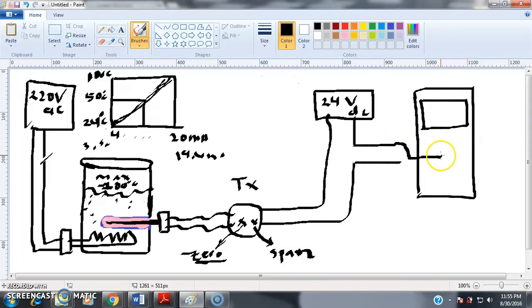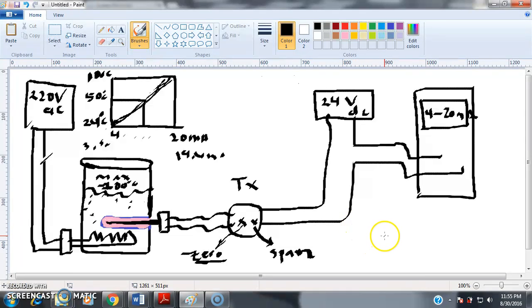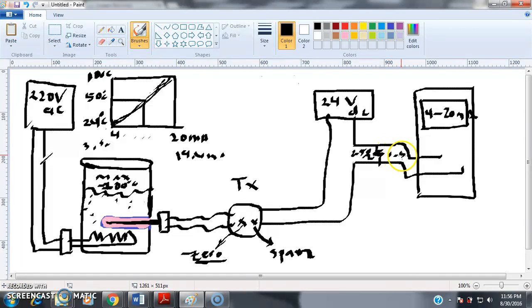You connect one line on one side and the other on the other side of the break, giving you a signal output which goes from 4 to 20 milliamps. If the temperature is 24 degrees you'll have 4 milliamps, and at 100 degrees you'll have 20 milliamps. If you want to read voltage instead, you convert current to voltage by putting a 250-ohm resistor in the loop, giving an output of 1 to 5 volts.